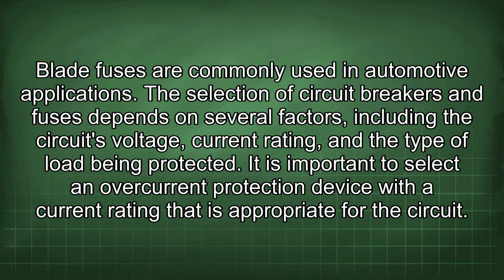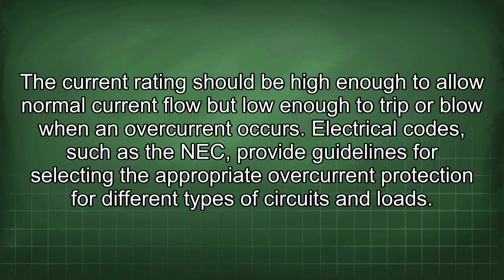The selection of circuit breakers and fuses depends on several factors, including the circuit's voltage, current rating, and the type of load being protected. It is important to select an overcurrent protection device with a current rating that is appropriate for the circuit. The current rating should be high enough to allow normal current flow, but low enough to trip or blow when an overcurrent occurs.